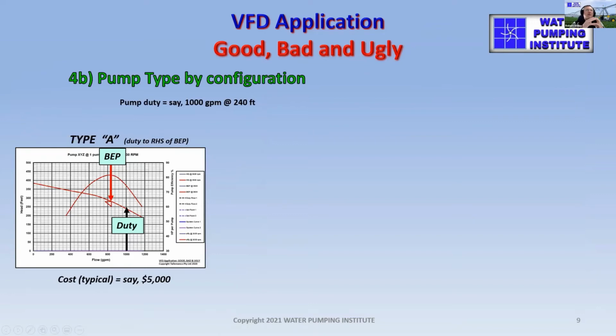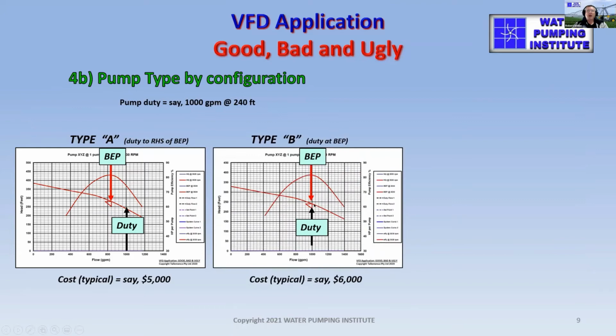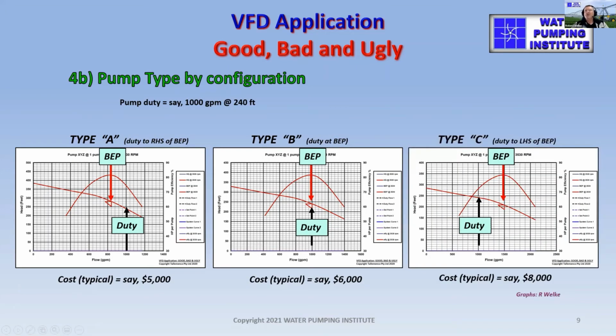So in keeping with that, we're going to define, for the purposes of this presentation, 3 types of pumps. The type A pump has its duty to the right-hand side of best efficiency point. A type B pump will have its duty at the best efficiency point, and all theory, every course you go to will tell you this is the ideal scenario, right? Always aim to have your pump duty at the pump best efficiency point. But that doesn't apply to VFDs, trust me, and you'll see why. And type C pump, where the duty is to the left-hand side of the best efficiency point.